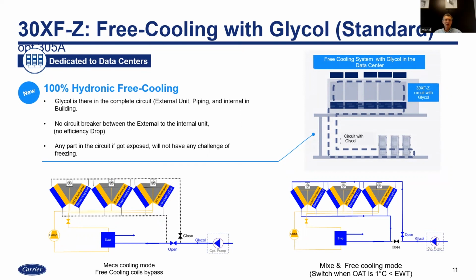So this valve is closed, this one is open. This is just a straight cooling chiller. But if there is an opportunity for free cooling, as soon as ambient temperature is below the return water temperature, so imagine if return water temperature is 30 degrees C and ambient temperature is 25, even if you want to produce 20 degrees C at the end of the process, you can start to pre-cool your water with those hydronic coils, and then continue the cooling with mechanical cooling if needed.